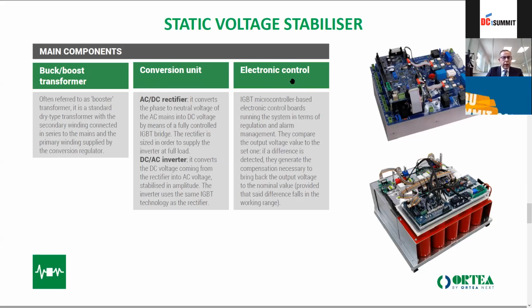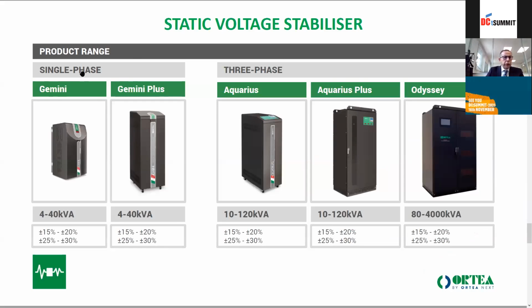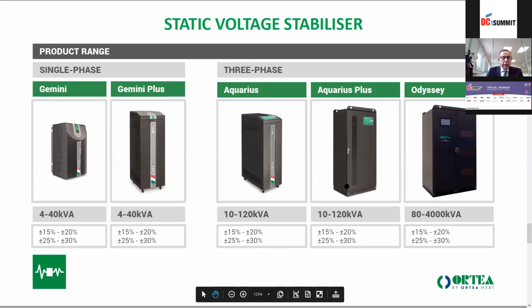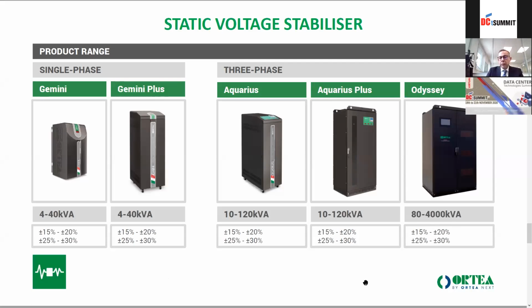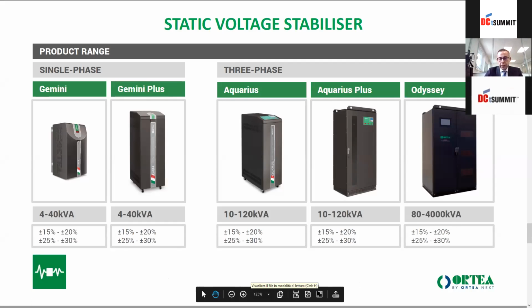So the brain will always analyze the situation, see how is the heart, and give the order to the conversion unit, which is not the regulator in this case, but it is the electronic regulator, to add or reduce the necessary voltage for the steady output. So in this range, we do have single and three-phase. We can reach in single phase 40 kVA maximum. Here we have always a symmetrical variation. We don't have asymmetrical variation because the IGBTs do work only on a simple and one way and cannot be asymmetrical. The three-phase can reach, as you can see, 4,000 kVA. So this is the static units.